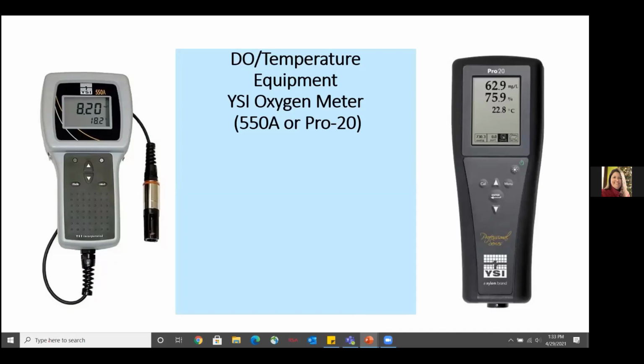So we have 2 types of meters that we use. We have YSI 550As, which is this grayer one on the one side, and then we have Pro 20s. The 550As have the cord that you drop down into the water with the sensor at the end directly attached. You can't detach them. The Pro 20s have a cord that detaches, which is just sometimes nice. That junction can stay safe by being able to remove the cord. Or if the cord breaks, we can just replace the cord and the whole unit doesn't need to be replaced.